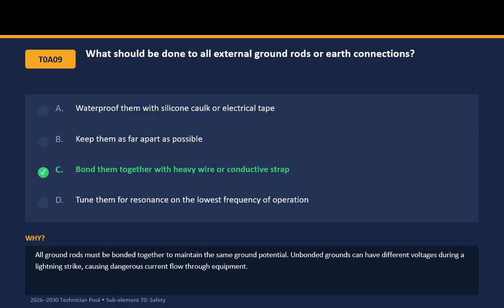What should be done to all external ground rods or earth connections? C. Bond them together with heavy wire or conductive strap. All ground rods must be bonded together to maintain the same ground potential. Unbonded grounds can have different voltages during a lightning strike, causing dangerous current flow through equipment.